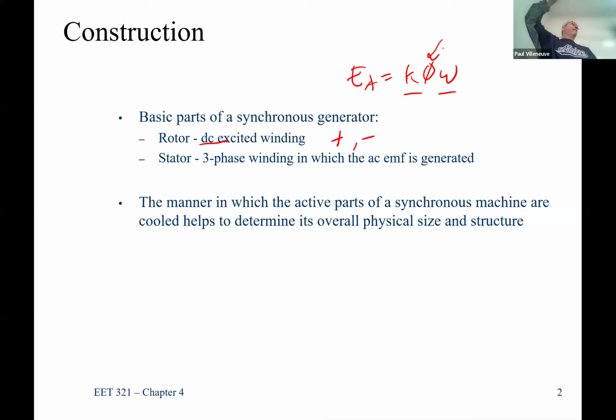Okay. Remember, the biggest generator that I know of in the Northeast is at Millstone. It's a 1500 MVA generator. That generator's nominal voltage is 25,000 volts, but it's got almost 50,000 amps of current. So you still need pretty massive copper to do it. But if you ran that at 480 or 13.8, it would not be practical to build a machine that can move that amount of current.